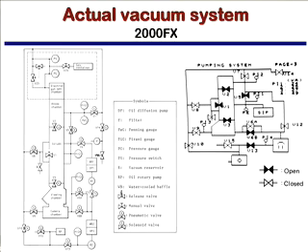There's a listing of pressure gauge readings on the modern microscopes. Those will be in Torr. In the case of the 2000 FX, they just read the currents running through those gauges. Lower current, better vacuum. Okay? And so you just learn for your own microscope which things need to be at which level in order for things to be operating properly.